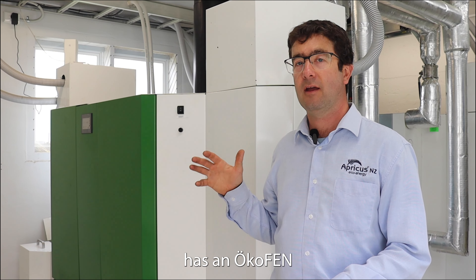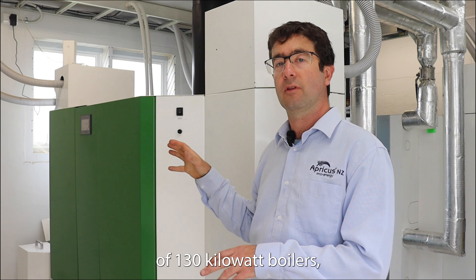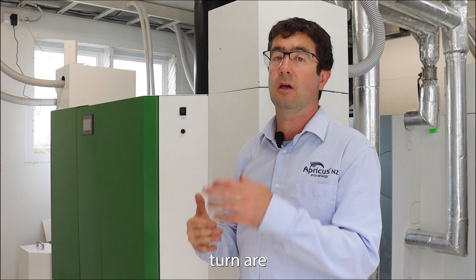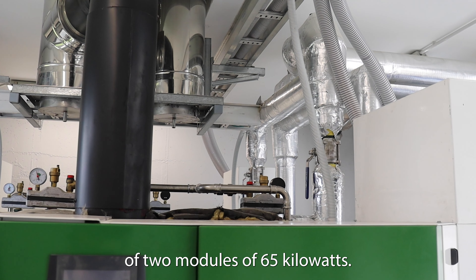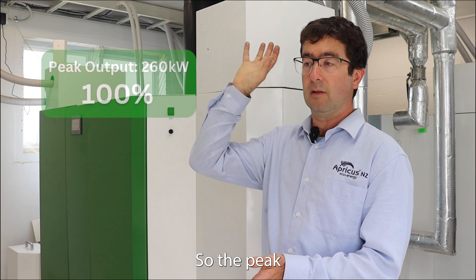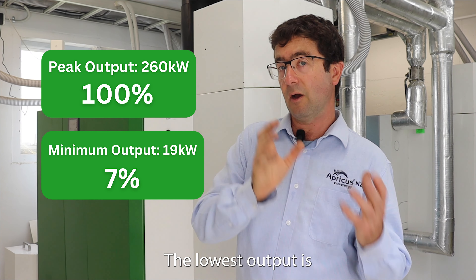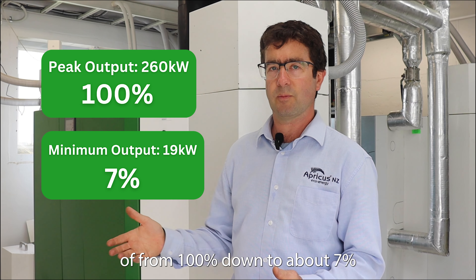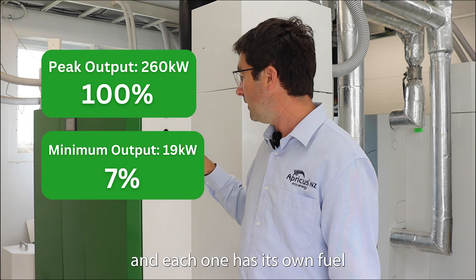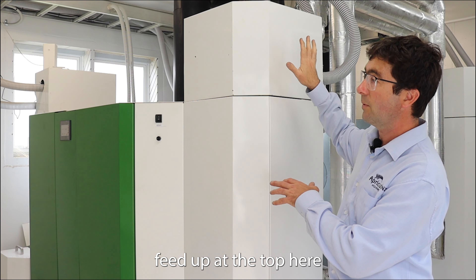Edgecombe College has an ÖkoFEN 260 kilowatt system made up of two pairs of 130 kilowatt boilers, which in turn are made up of two modules of 65 kilowatts. We've got a huge modulation range — the peak output is 260 kilowatts, the lowest output is 19 kilowatts, so that's a modulation range from 100% down to about 7%. Each one has its own fuel feed up at the top here.